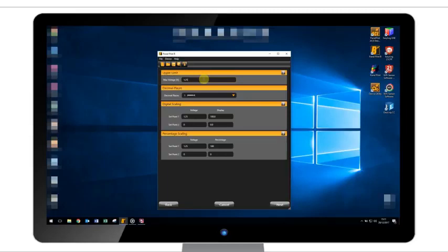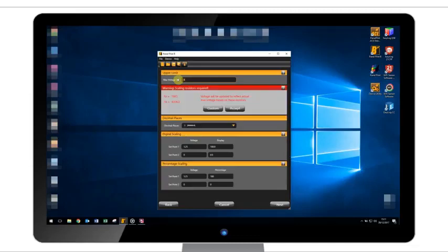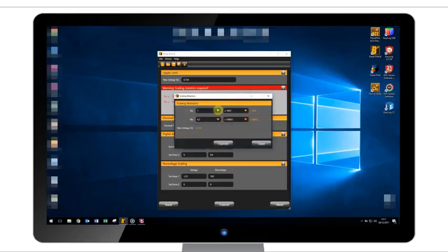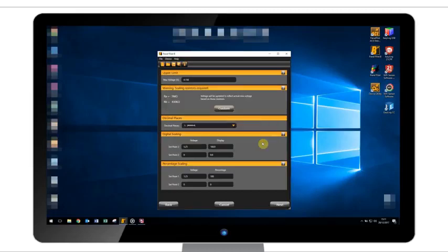Choose your maximum voltage and scaling settings. By default, the maximum voltage is 1.25. Any value above this will require the addition of scaling resistors. If these are required, the software will prompt you like this and suggest suitable values. You can either accept these or customize them yourself. Please note that the maximum voltage will change dependent on your choice of scaling resistors.